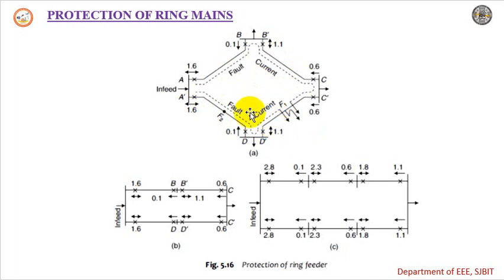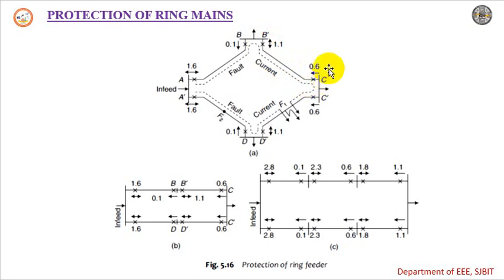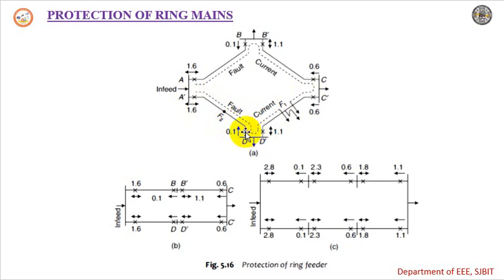In such a case, relay A is non-directional. The directional relay at B sees normal current flow so B will not trip. B' is non-directional. C is directional — since current is flowing in the normal direction, C will not trip; it would only trip if current flowed in the opposite direction. A' is non-directional. D is a directional relay — it would trip only if current flows in the specific trip direction, but now the current is flowing in the opposite direction, so D will also not trip.